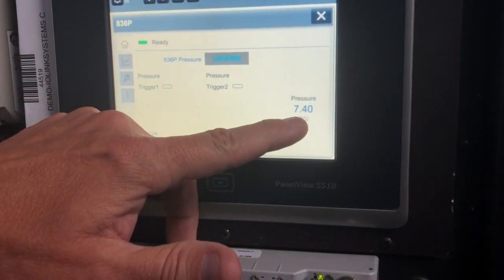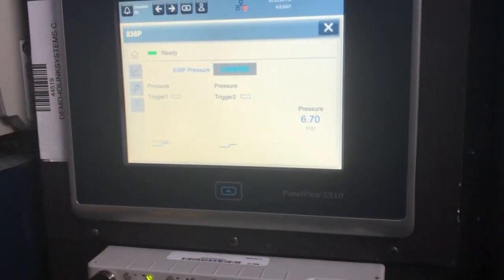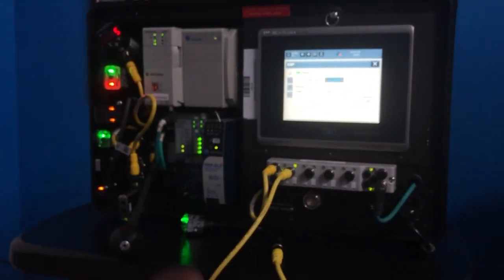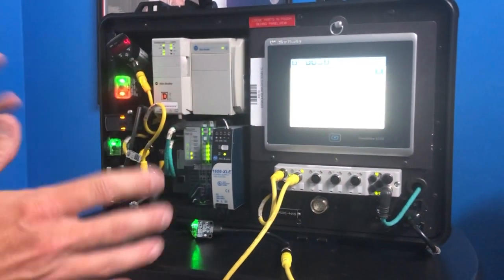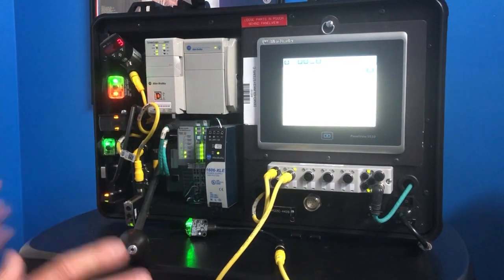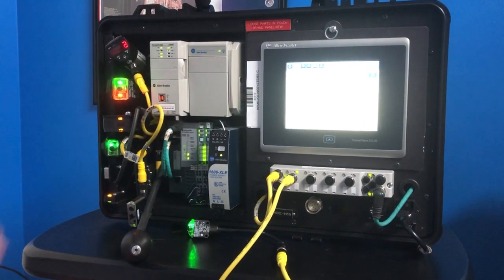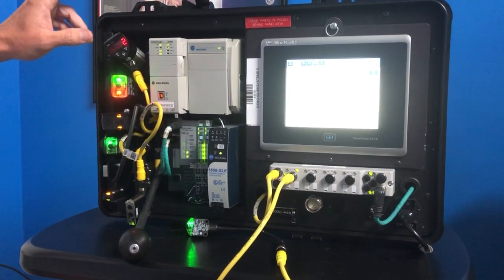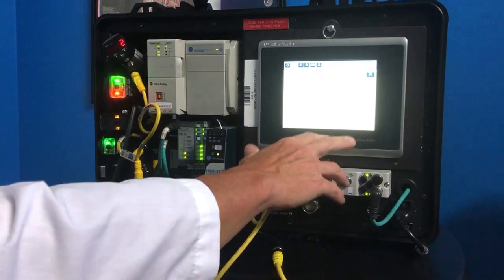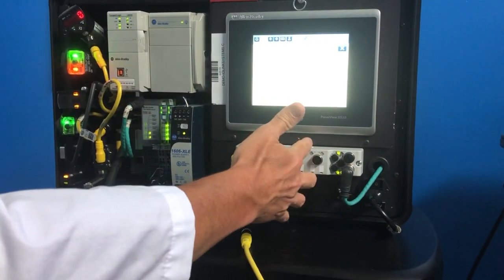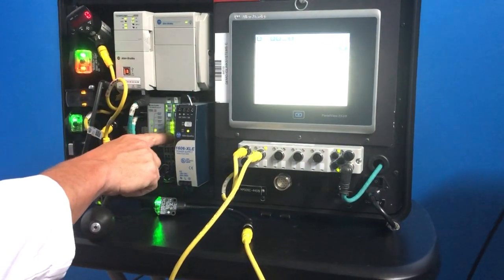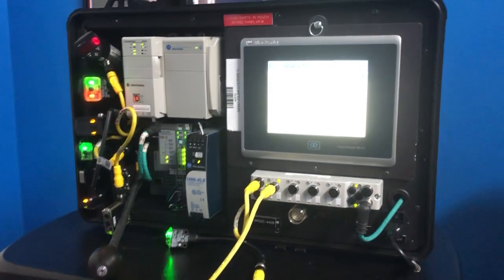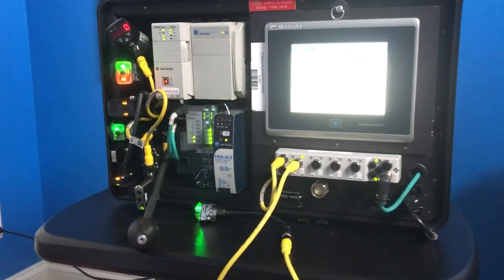Now, in the past, the way we did that is we would have a 4 to 20 milliamp signal coming out of this, going into a 4-20 milliamp card, and then basically, we'd have to scale that. With IO link, there's no scaling whatsoever. Literally, you take the sensor, you plug it up to either your IO link master module here, the on-machine connectivity, or point IO. But either way, it comes in as a decimal value. We don't scale anything anymore.